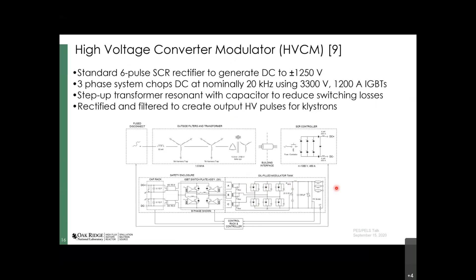I'm going to go a little more in depth on the HVCM, or high voltage converter modulator. This is an overview of the 4 major pieces of equipment. Outside of the SNS facility, you may have seen on your tour these bright yellow boxes. Those are the utility power transformers associated with the system. We basically take the 13.8 and step it directly down to 2100 volts RMS, and that's the power we feed into the building. Once inside, we go into this silicon controlled rectifier 6 pulse system to convert it into DC power, and that allows us to provide power levels just over 1 megawatt of average power.